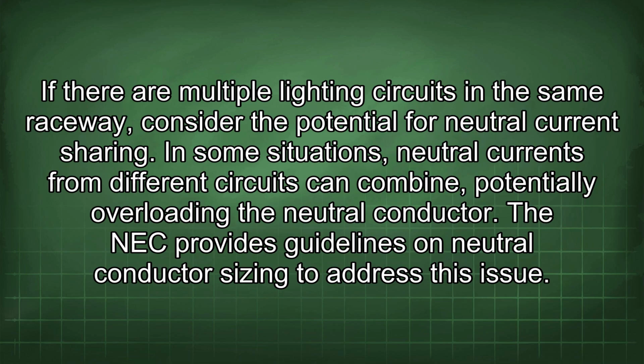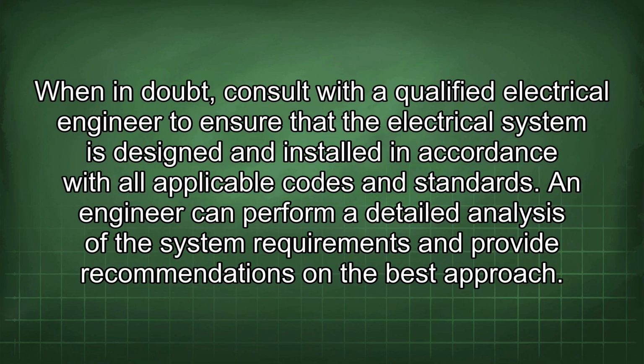If there are multiple lighting circuits in the same raceway, consider the potential for neutral current sharing. In some situations, neutral currents from different circuits can combine, potentially overloading the neutral conductor. The NEC provides guidelines on neutral conductor sizing to address this issue. When in doubt, consult with a qualified electrical engineer to ensure that the electrical system is designed and installed in accordance with all applicable codes and standards.